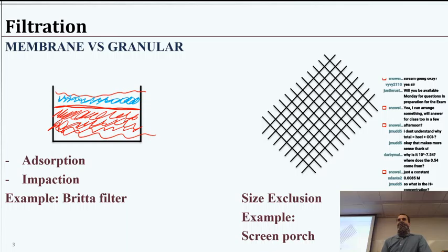So all the particle settling we were just talking about, if you imagine having tiny little pores through the sand grains, you have like a million little channels which are acting as sedimentation basins or adsorption sites. So the particles, instead of sedimenting in our big sedimentation chamber, as the water flows through and is collected, we end up with lots of places for the particles to get caught or stick or to sediment. So most of that's going to be what we would call adsorption or impaction.